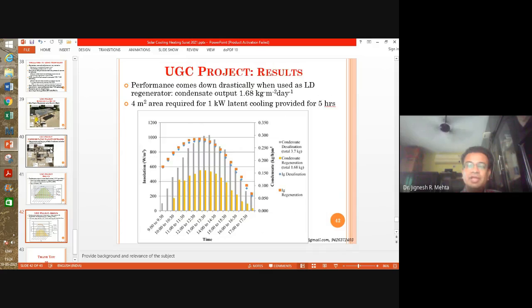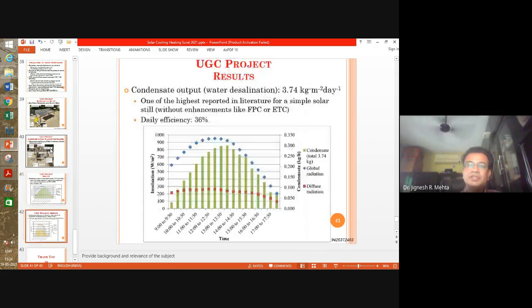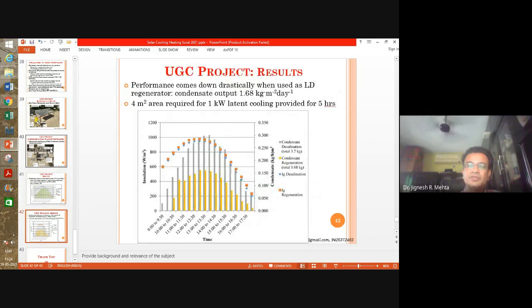But when you use it for liquid desiccant regeneration, the output reduces drastically because the temperatures become much higher. You can see it has reduced from 3.74 to 1.68, even less than half of it. Right? This is because the temperatures will remain higher, because the vapor pressure is not so high when you use a salt solution, right? So according to that assessment, 4 meter square area would be required if you want to provide 1 kilowatt of latent cooling. This is talking about only latent cooling or dehumidification for 5 hours.